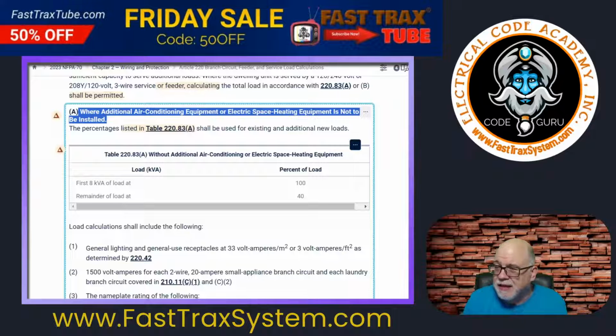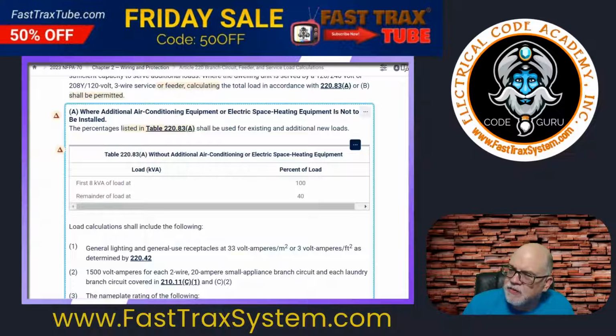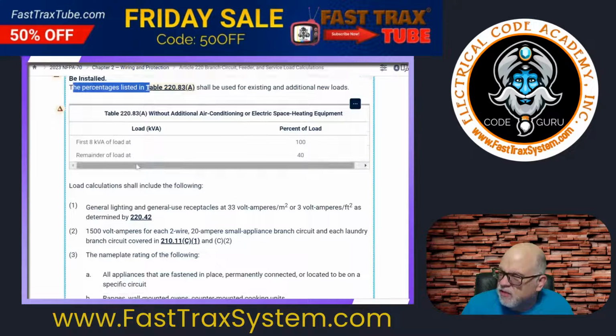Okay, so a lot of people got confused with that and said, "Well, no, I'm not adding additional ones." And if you go down and we're going to look at the list here, they're saying, "Well, if I'm not adding additional ones, then I don't have to account for the ones that are already there." But you do have to account for the ones that are already there. All right, so let's look at it here. It says the percentages listed in table 220.83(A), and that's this table right here, shall be used for existing and additional new loads. All right, so what does this actually say?